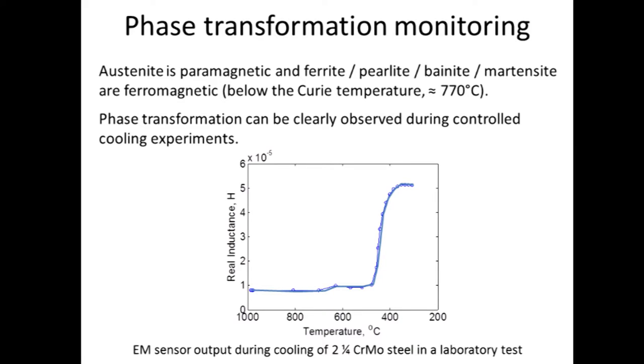I'd like to talk a bit about where things have got to and then some of the scientific basis of how this field is developing. So we take phase transformation monitoring — this is very much looking at in-situ measurements during steel processing. There are very large signal changes when we go from an austenitic phase to any of the product phases: ferrite, pearlite, bainite, martensite — provided we're below the Curie temperature, we go from a paramagnetic phase to a ferromagnetic phase and therefore get large signal changes.